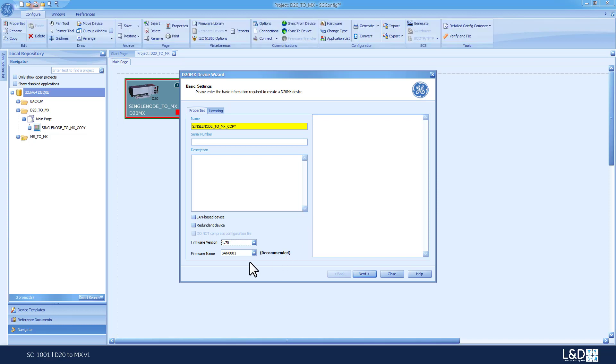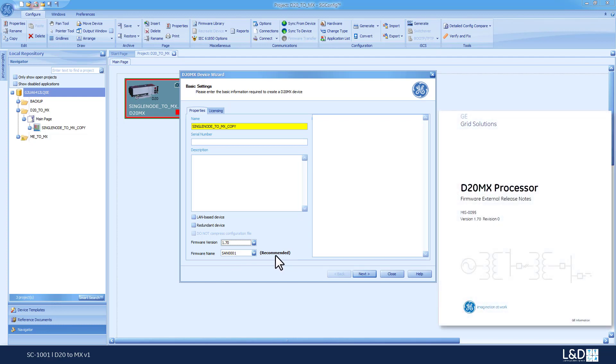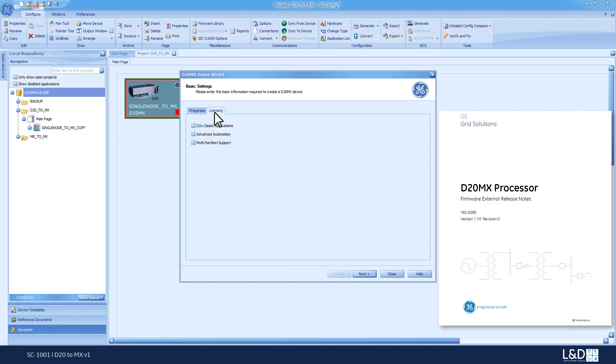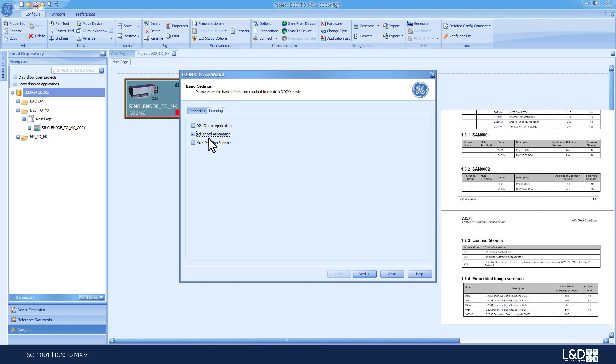By default, the firmware SAN0001, which is the recommended firmware, is selected. Under the Licensing, you might want to select the appropriate license based on the number of applications that you are using and the type of applications that you are using. If, for example, you are using Logic Links in your application, that's where you need to review the release notes for D20MX firmware release notes for version 1.7. And basically, you go to the licensing page.